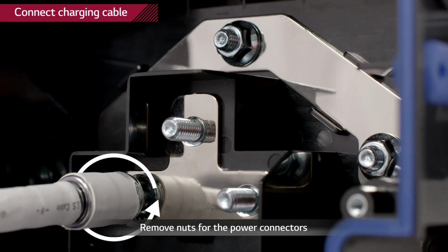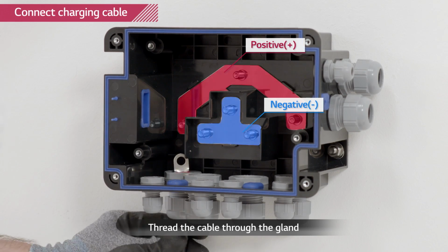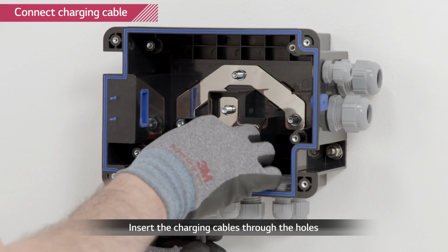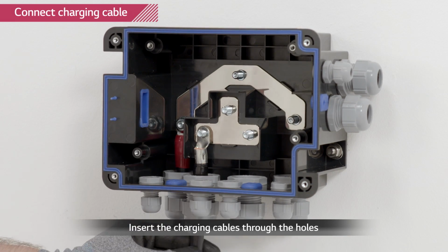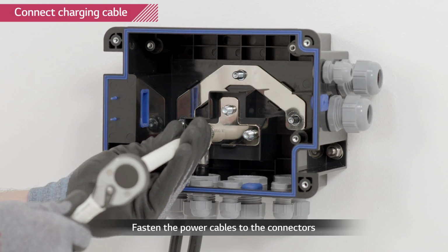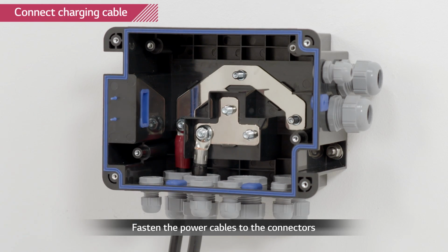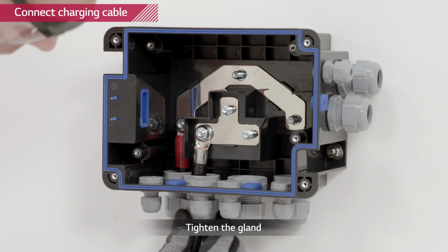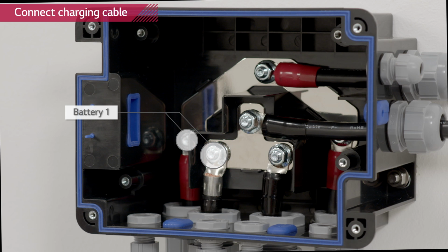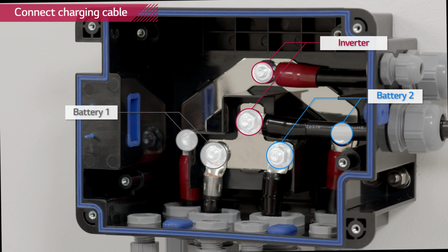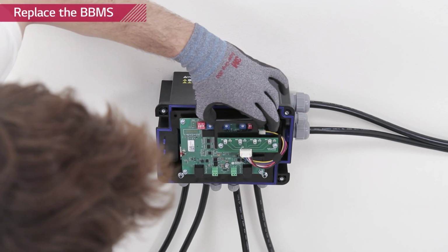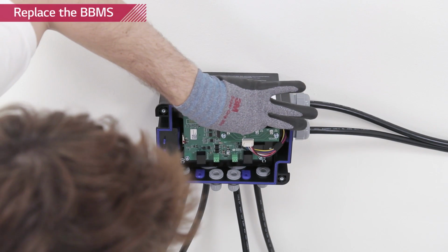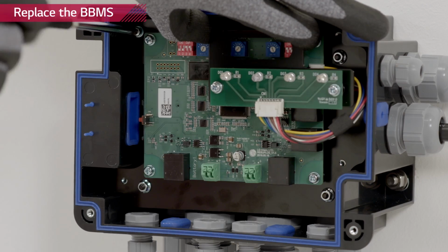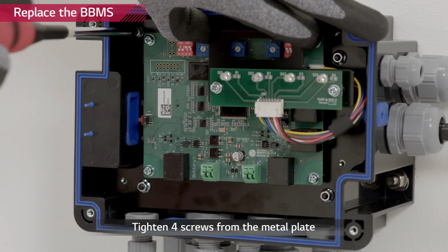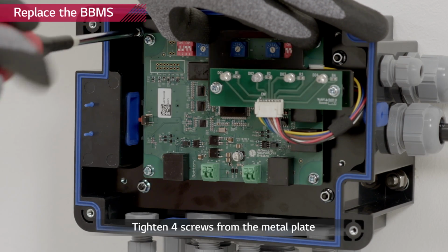Loosen the large glands and the nuts of power terminals. Thread the power cable through the large glands and connect each cable to its corresponding terminal. Tighten the nuts of the power terminals first, then the glands. After all power cables have been connected, reattach the bank BMS and tighten the M4 screws with a torque of 1 Newton meter. The bank BMS must be handled very carefully.